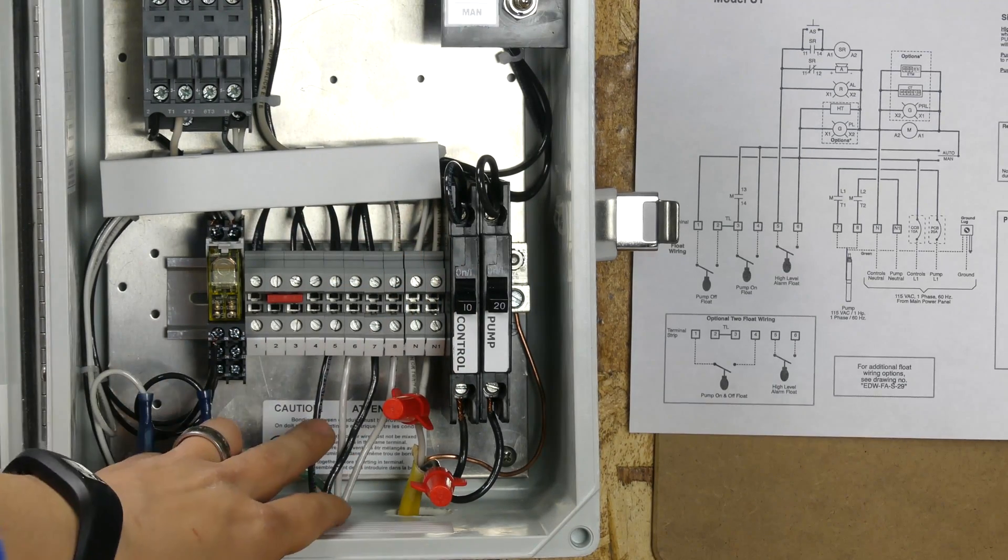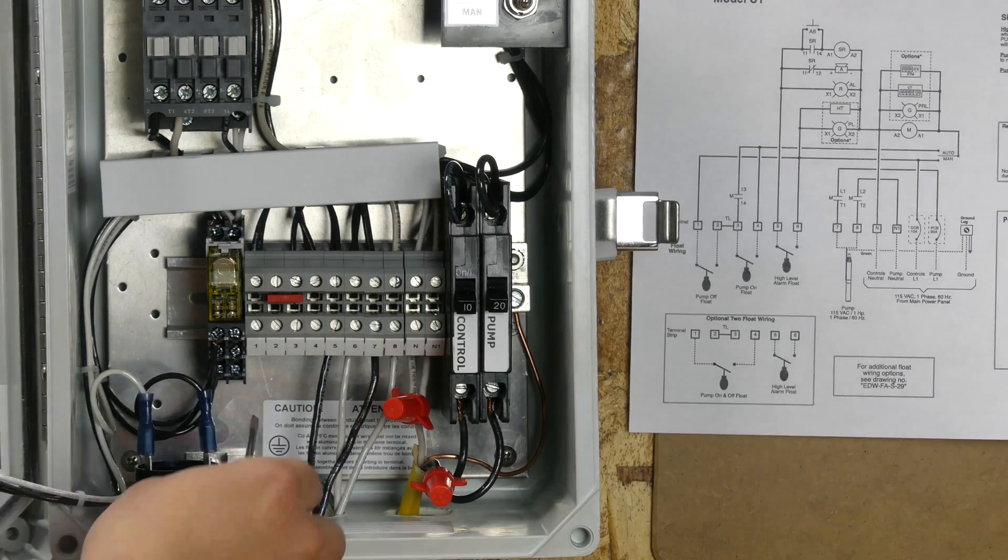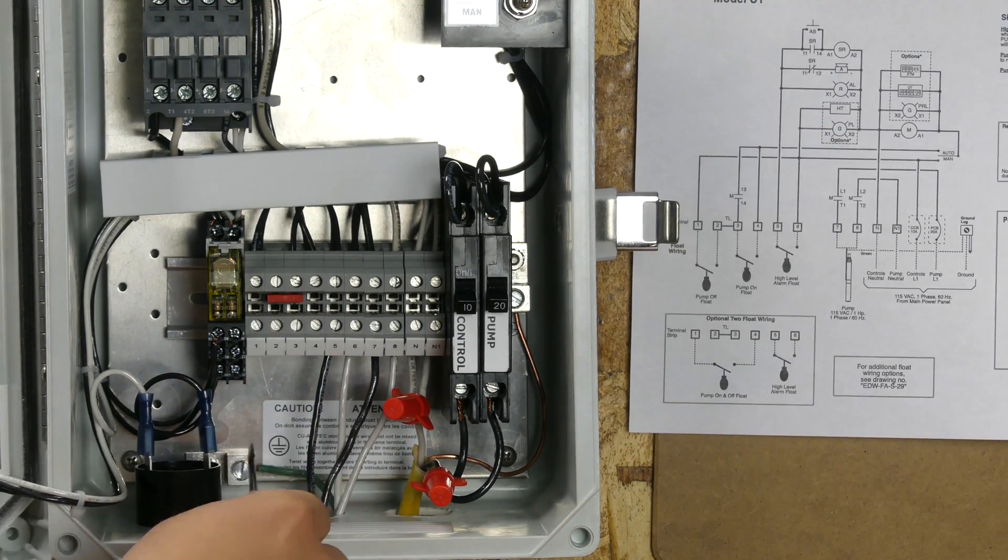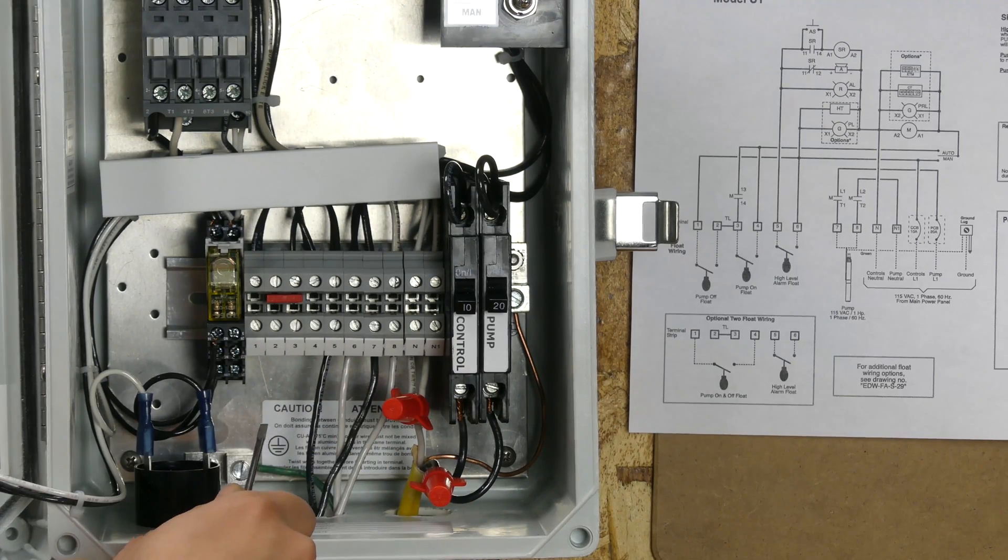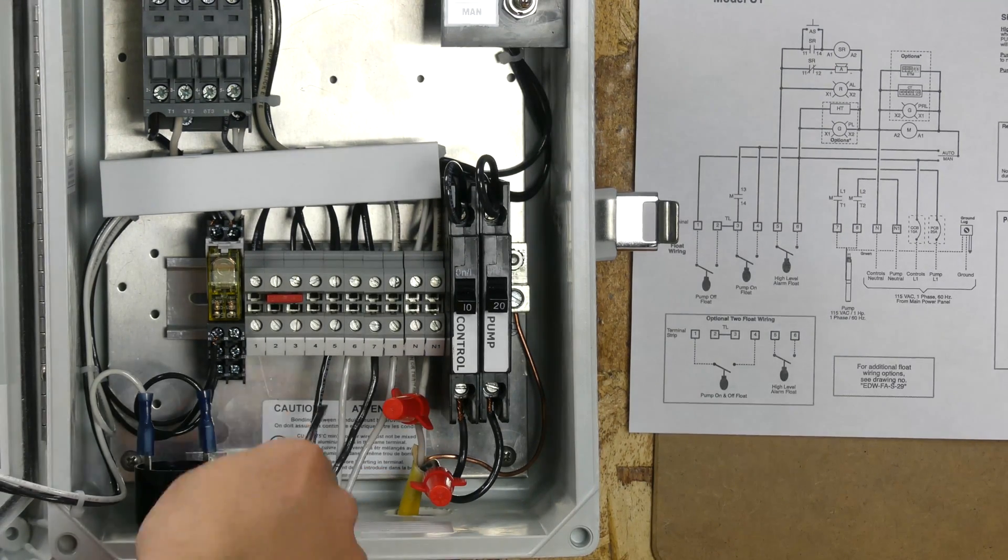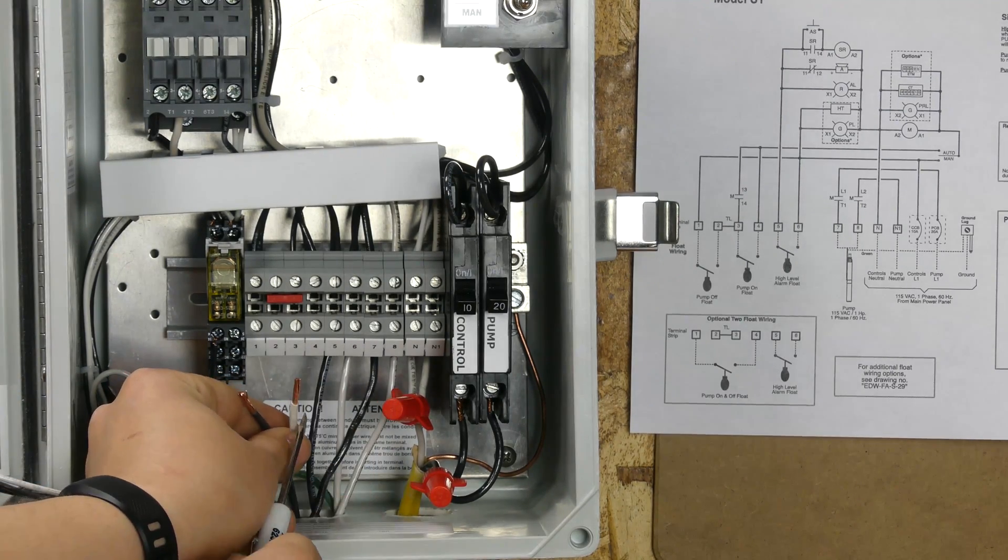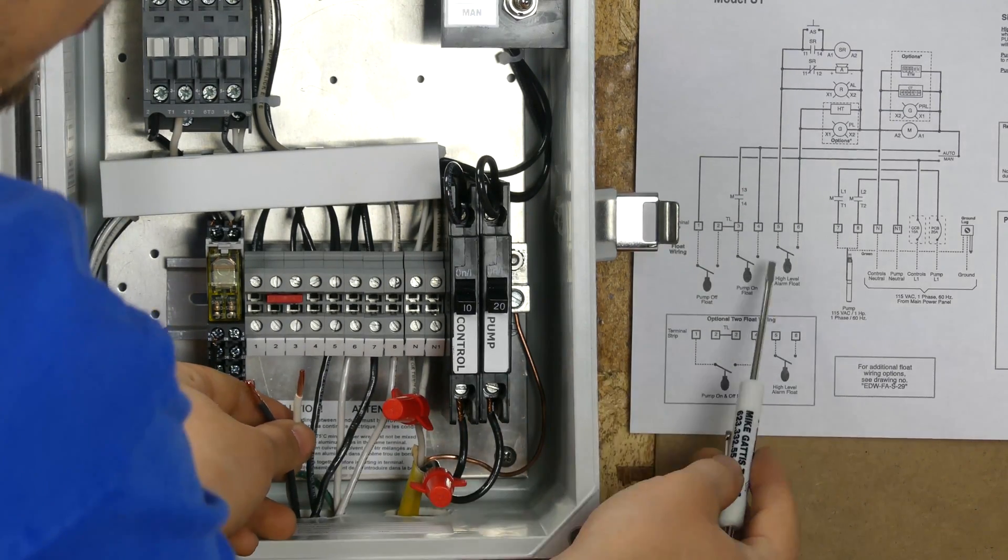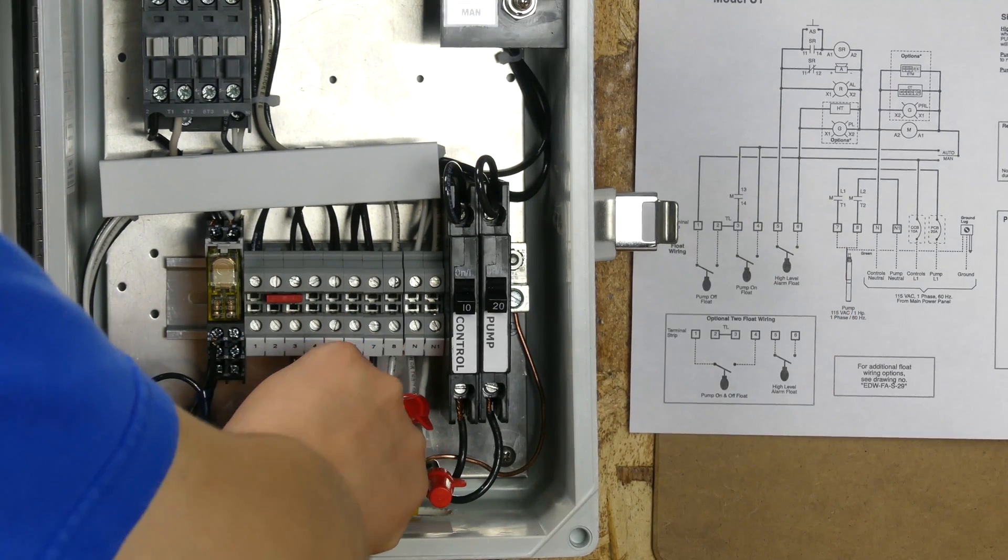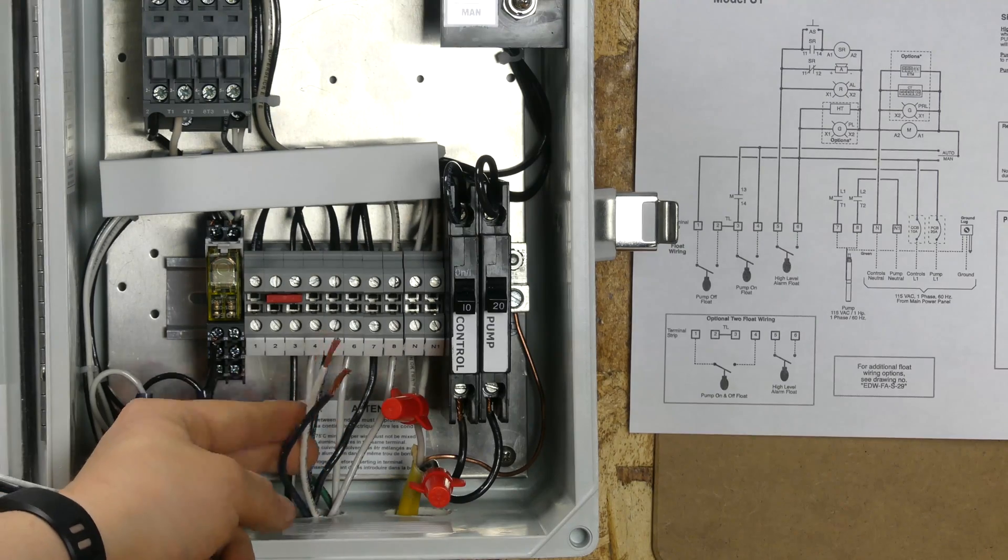Another thing to remember with float switches is in this configuration it really doesn't matter which wire goes to which side, so I could have flip-flopped these and the panel will still work just fine, but we'll just stick with the white and black pattern. The next float we're going to be hooking up here, this is going to be our middle float. This is the pump-on float.